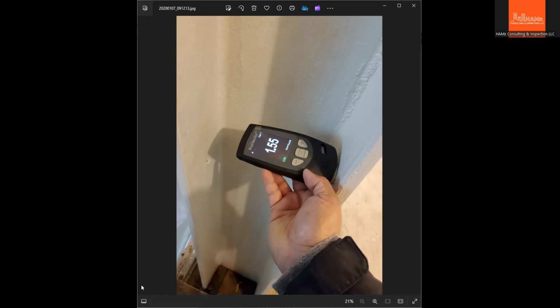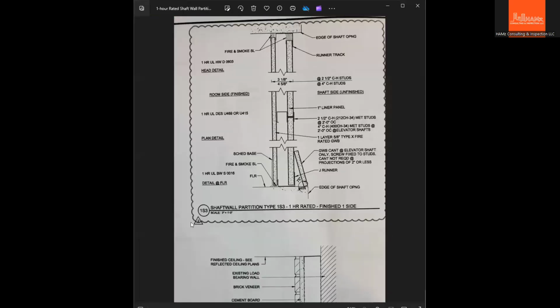an alternative protection like this one. So this is a shaft partition wall. This is an hour rated. This is the detail of installation for an hour rated enclosure or protection of fire enclosure. So it should be a layer of 5/8 as per this detail, a layer of 5/8 on both sides of the stud, and a 1 inch thick liner panel. Yeah, it's 1 inch thick, and this is 5/8 Type X fire rated gypsum wallboard.